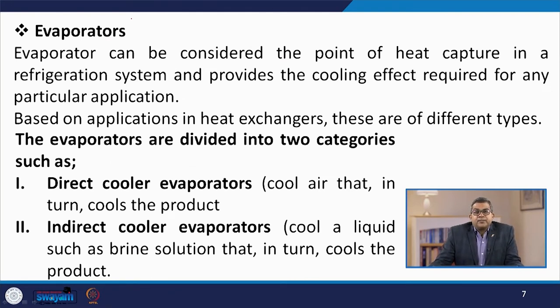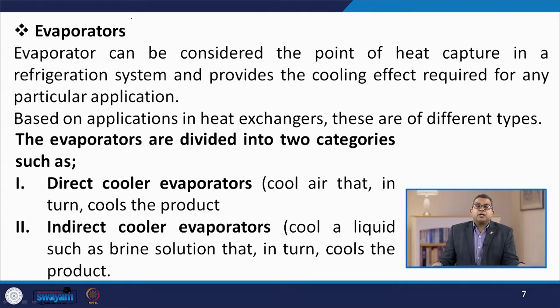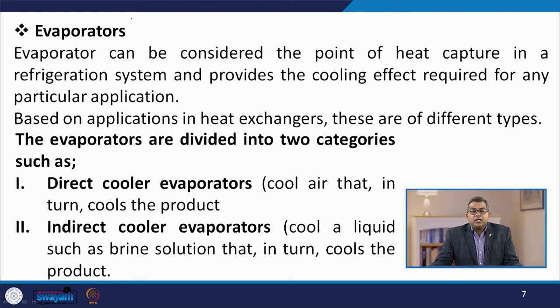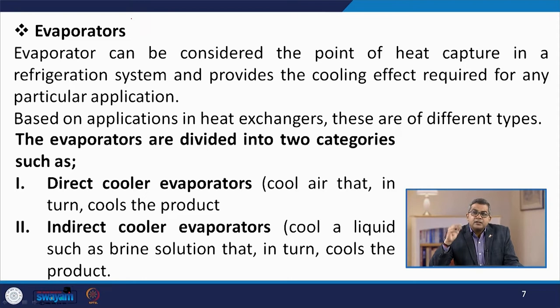Let us talk about the evaporators. Evaporators can be considered the point of heat capture in a refrigeration system and they provide the cooling effect required for any particular application. Based on application in heat exchangers, there are different types of evaporators. The evaporators are basically divided into two categories: direct cooler evaporators, which cool air that in turn cools the product, and indirect cooler evaporators, which cool a liquid such as brine solution that in turn cools the product.